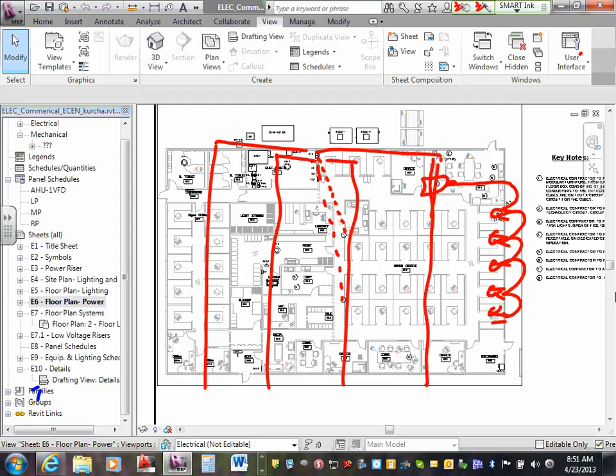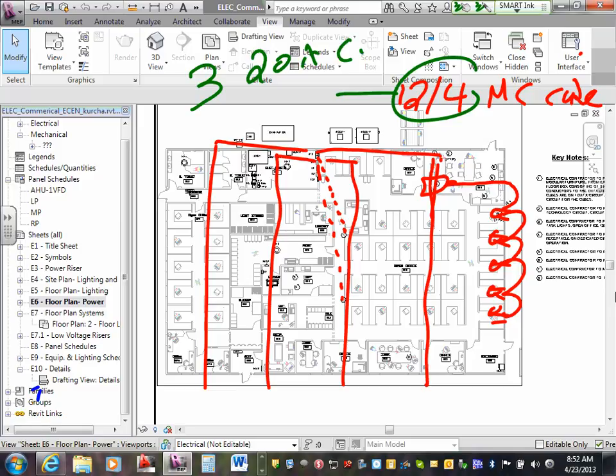Depending how many. And here's my advice for you guys: when you use an MC cable, unless they tell you you need a separate neutral, here's what you're going to be moving with: a 12-4 MC cable. 12-4, guys, will give you how many circuits? 12-4 will give you 3 circuits, 3 20-amp circuits. So if you're moving in this wall with 12-4 and you have up to 3 circuits, you can pick them up with one cable, take them all the way to a junction box, and shoot them all the way to the panel.